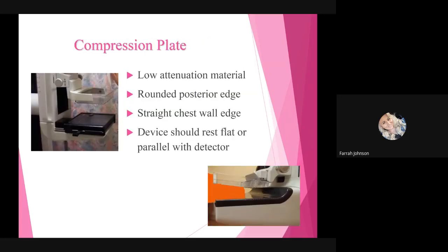Then that brings us to the compression plate. Your compression plate must be made of a low attenuation material so that it does not absorb a hefty amount of your photons. It must have a rounded posterior edge to help with patient comfort. It needs to have a straight chest wall edge, meaning the side of the paddle that is going to brush up against the chest wall needs to be straight. And the device should rest flat, or at least parallel, with the detector.